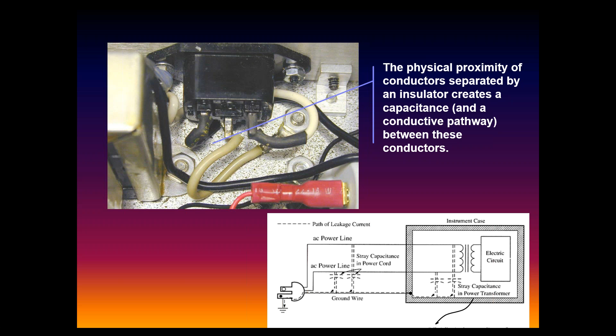You can measure this. Here we've got this old Valleylab ESU, and we measured its leakage current with an analyzer, getting about 81 microamps. You can also run it on an oscilloscope and look at the leakage current across the standard load, that's the small waveform here, with our 120 volts going in.